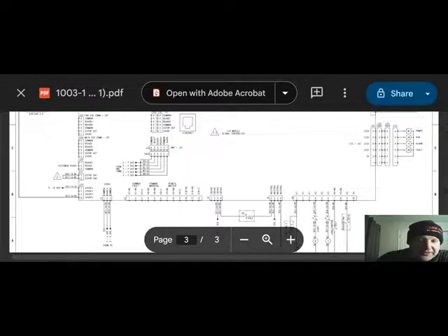So you would need to provide your own power source in here to the common from somewhere. Doesn't matter where. Could be an external power source. Could be from the 24-volt power supply inside the machine. Can come from basically anywhere. But as long as you don't exceed the rated voltage of these contacts, you're going to be just fine. So you bring your power source into the common here, and then that's going to flow back out via one of these two contacts, depending on what you want this thing to do.